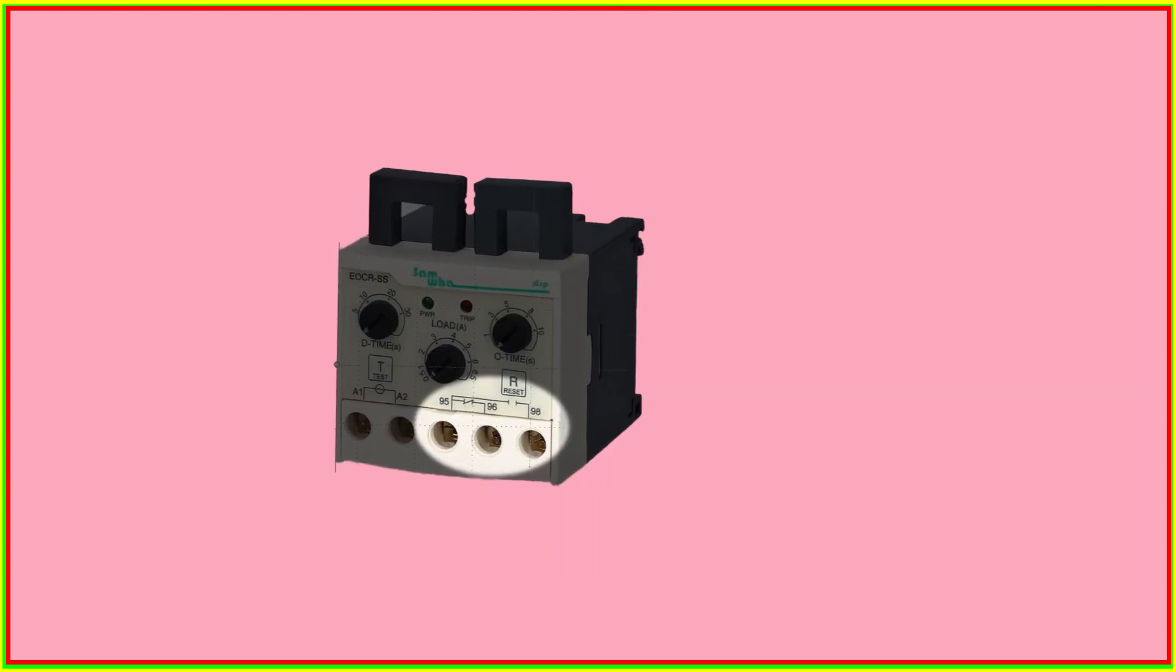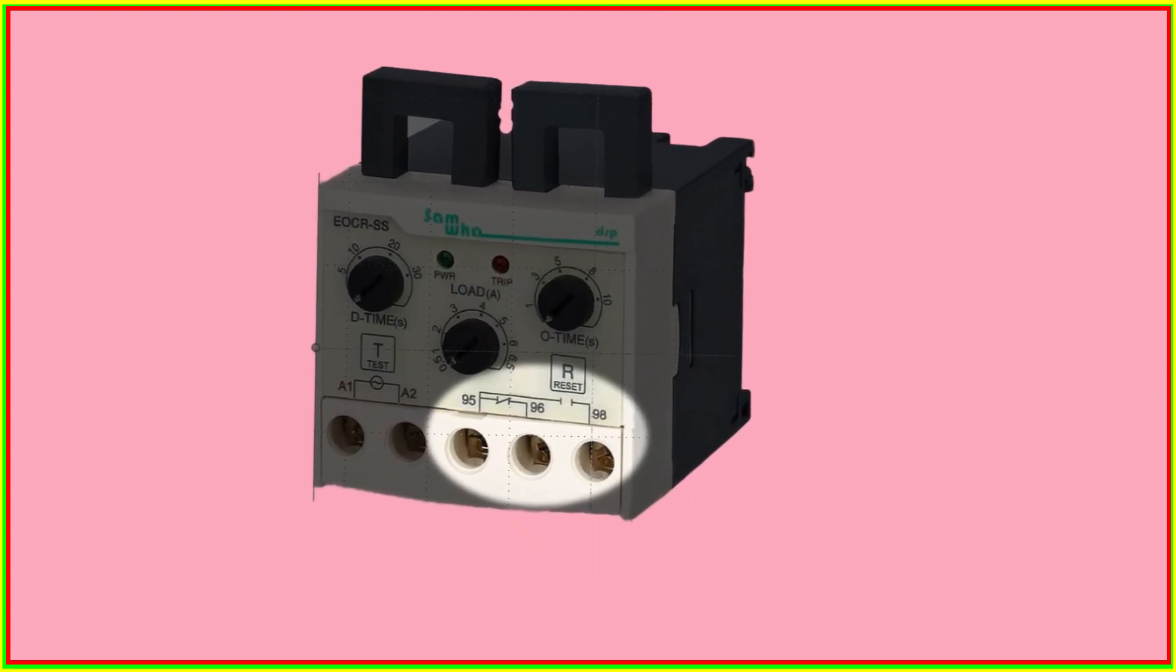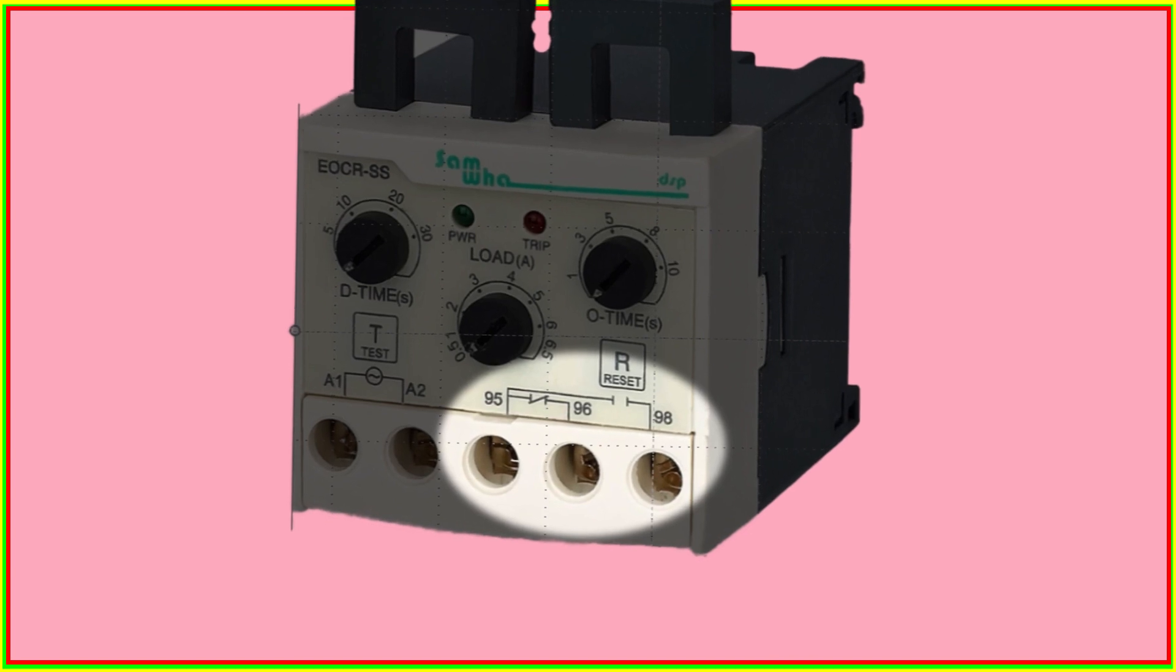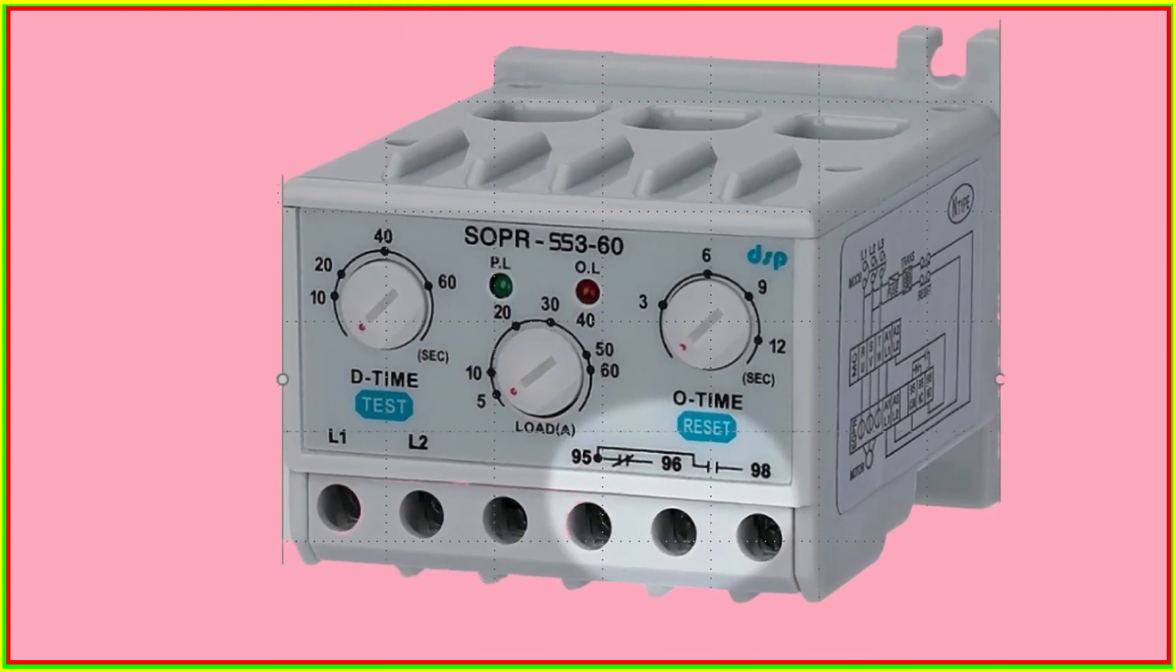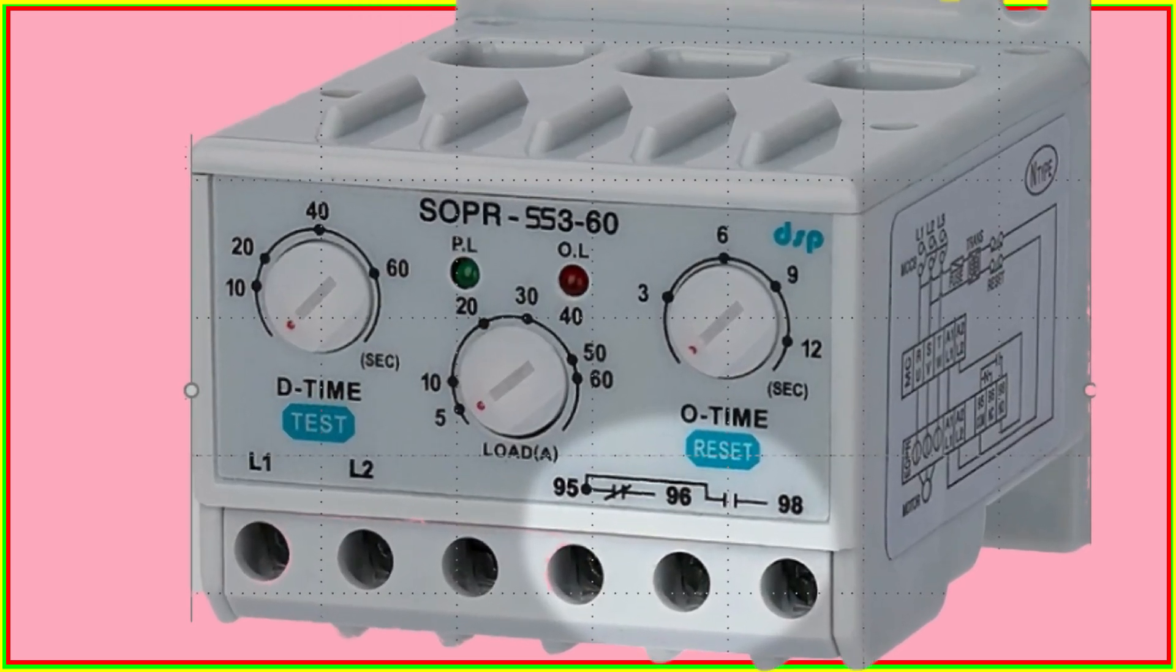Some overload relays have only three terminals, namely 95, 96, and 98. Terminal 96 serves as the common terminal, while terminal 95 is the normally closed contact and terminal 98 is the normally open contact.